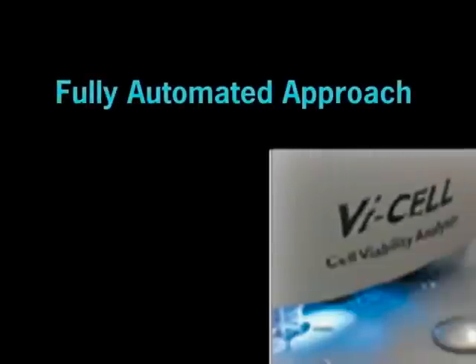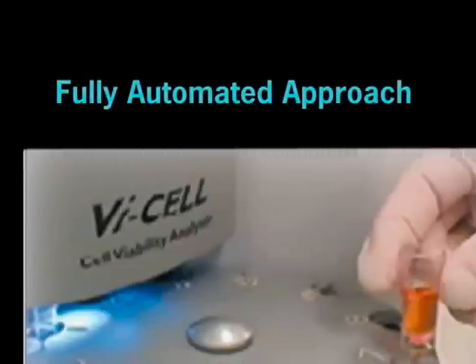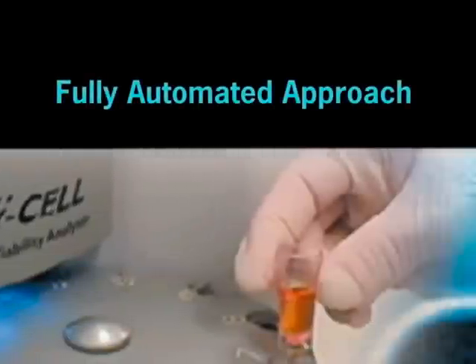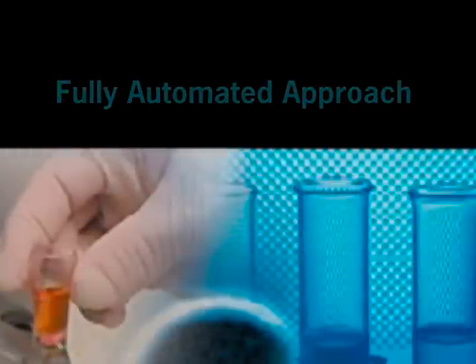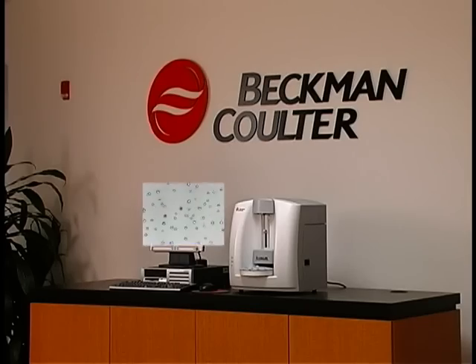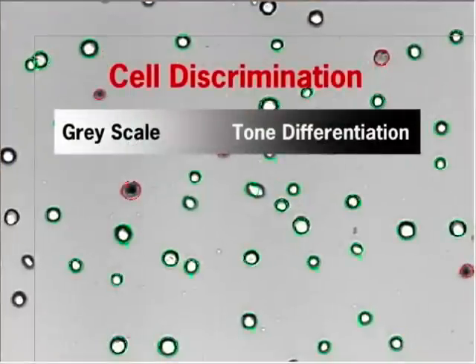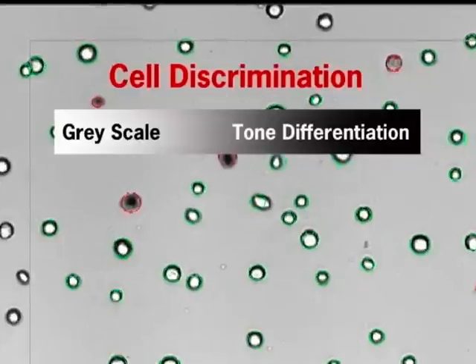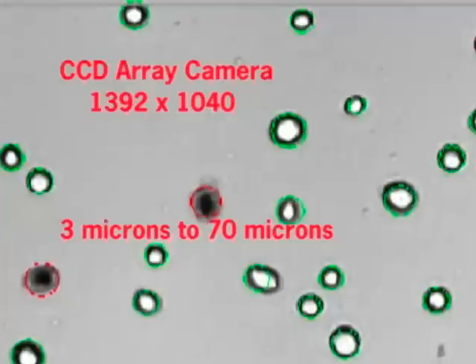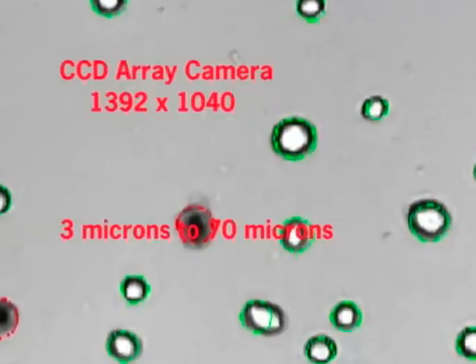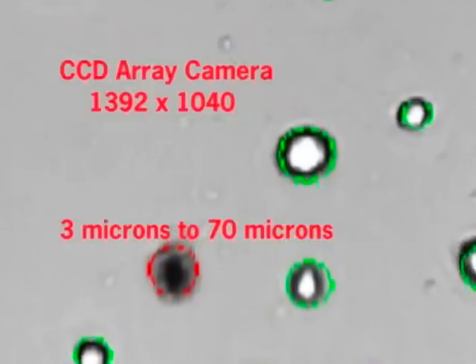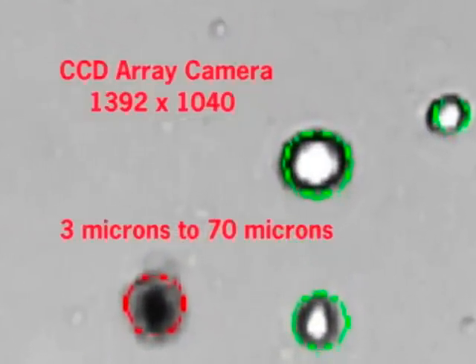The Vi-CELL XR instrument integrates the Trypan Blue dye exclusion method and digital imaging technologies. The images are then analyzed using a proprietary algorithm for continuous grayscale tone differentiation for cell variation discrimination. The system's autofocus feature, coupled with a 1392 by 1040 CCD array camera, allows for analysis of cells from 3 microns to 70 microns in size.